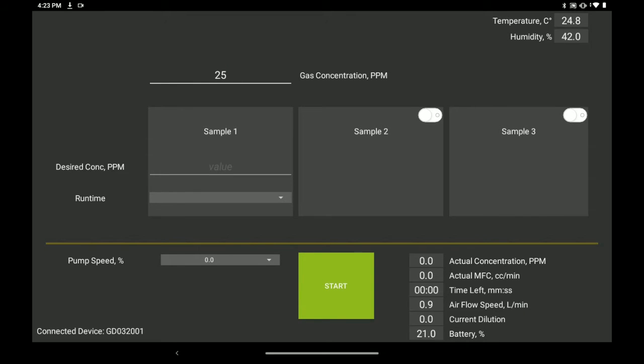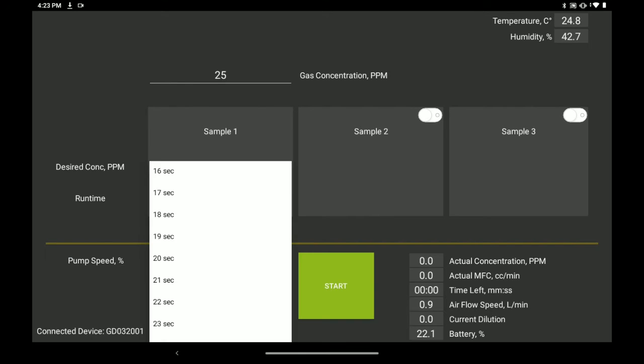Now I want to put in the desired concentration. We have a 25 ppm gas canister. We have an H2S sensor that has a range of 3 ppm. So I'm going to want my desired concentration to be 500 ppb or 0.5 ppm. I want to feed the unit this gas for 10 minutes. So I'm going to scroll down until I find 10 minutes and enter that in here.